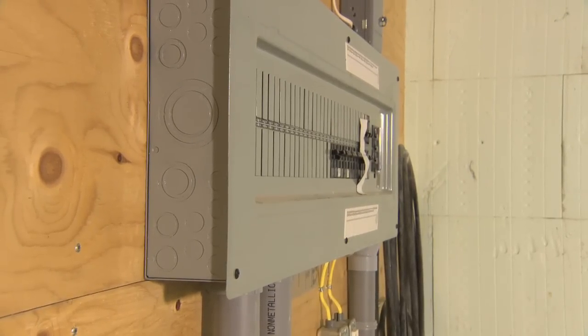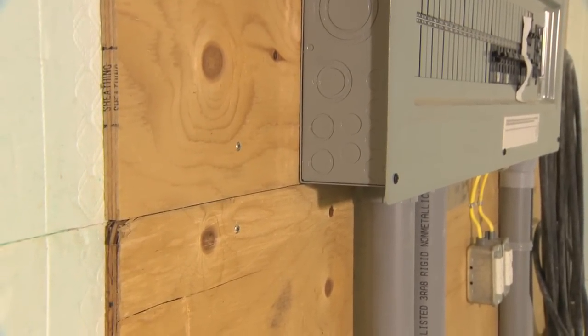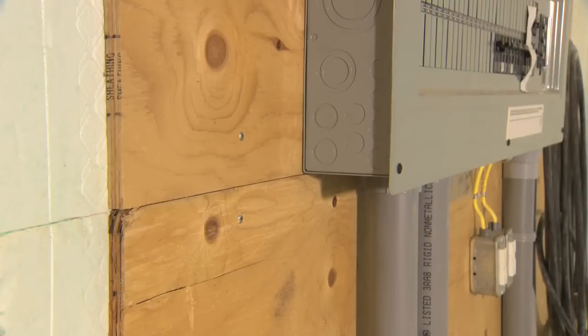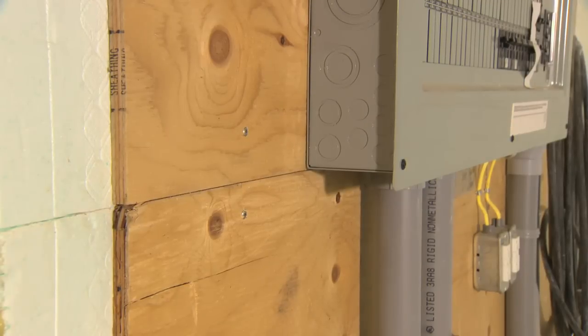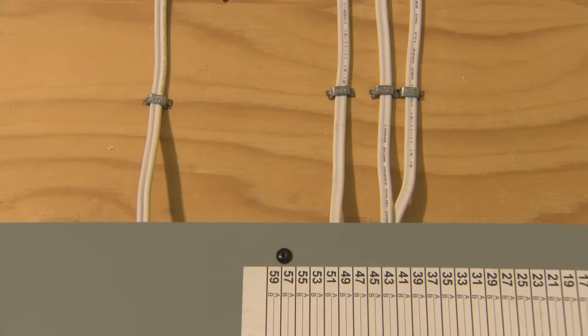When mounting the main panel onto a Nudura wall, it's recommended to use a minimum 1/2 inch or 13mm thick plywood base. You can attach the plywood directly to the fastening strips, or make a direct connection to the concrete wall if desired. The plywood base will also allow the electrician to staple the wires.